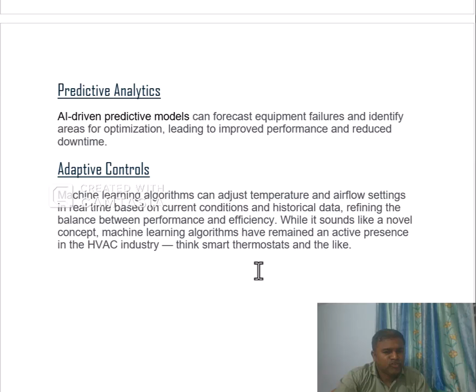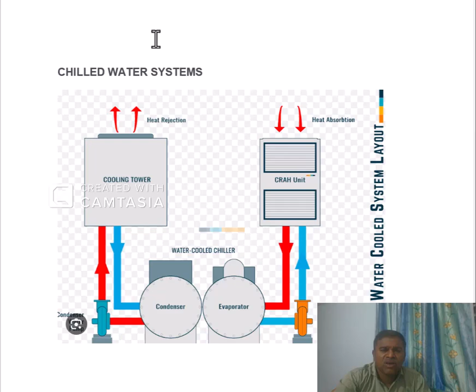Now look at the chilled water system. This is a cooling tower, this is a CRAH unit. Heat is absorbed and water is circulated using a pump, moving between the evaporator and the condenser. It takes the heat inside the data center and throws it out through the chilled water system.